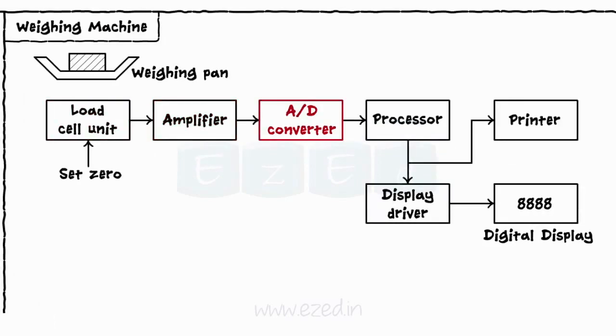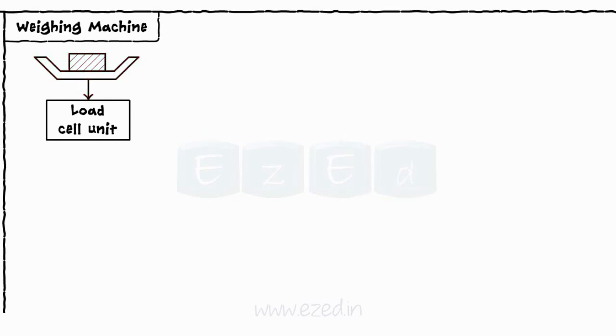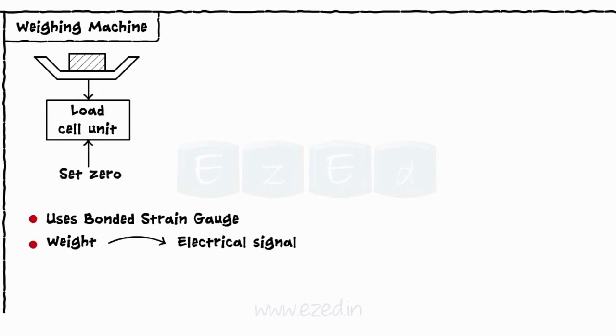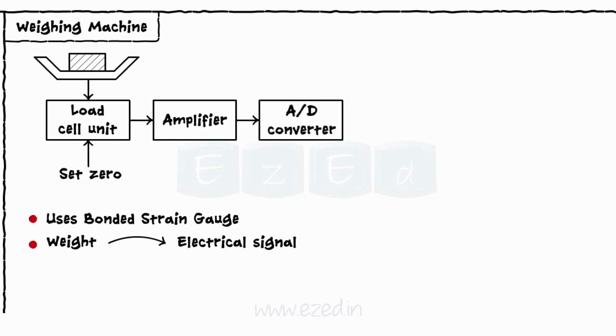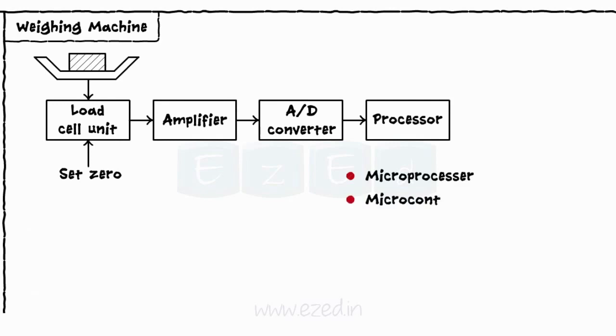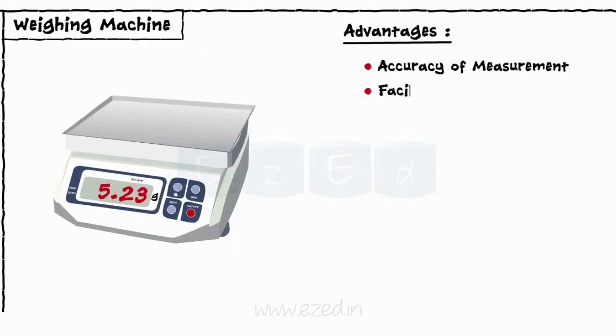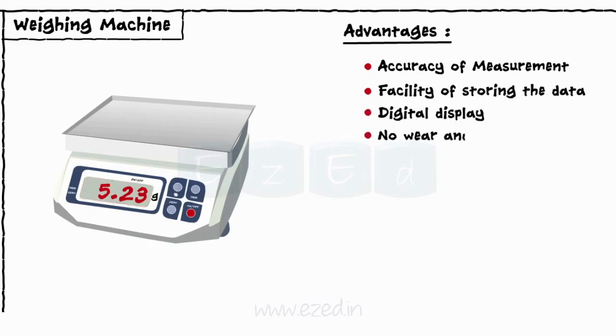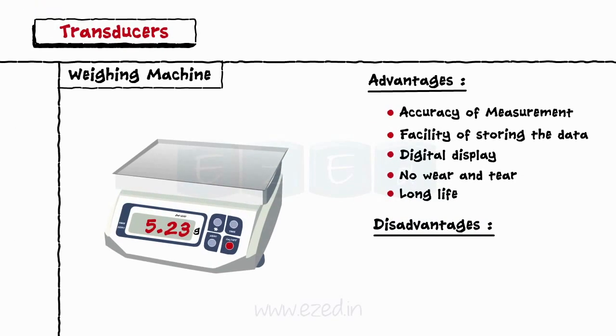Next, we will study about weighing machines. The different blocks of a weighing machine are load cell unit, amplifier, analog to digital converter, processor, display driver, display, and printer. The weighing pan is directly connected to the load cell unit. The load cell unit has a bonded strain gauge which converts the weight into electrical output. Zero setting adjustment is also provided with the load cell unit. Electrical output of the load cell unit is amplified by an amplifier and converted into a digital signal by an A to D converter. The processor, which can be a microprocessor or microcontroller, processes the input data, stores it in memory, and performs computational operations. The advantages of weighing machines are accuracy of measurement, facility of storing data, digital display, no wear and tear, and long life. The only disadvantage is the requirement of high initial cost.